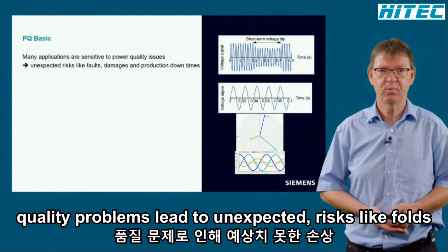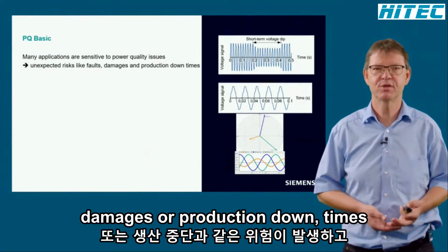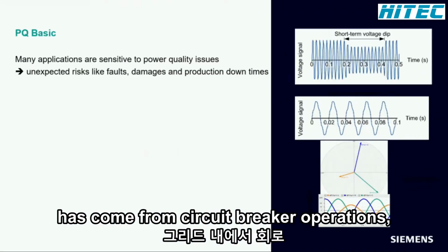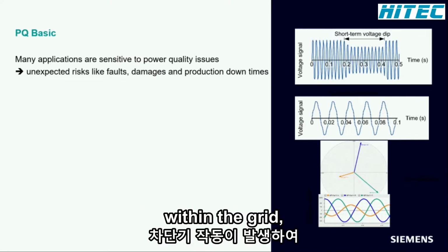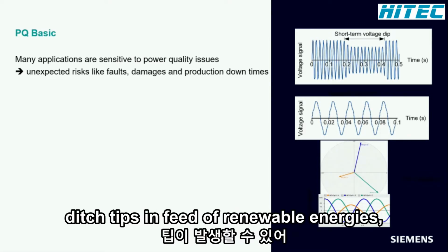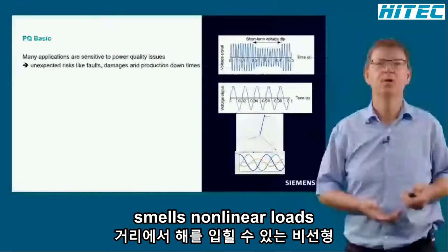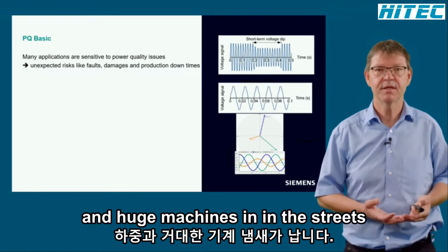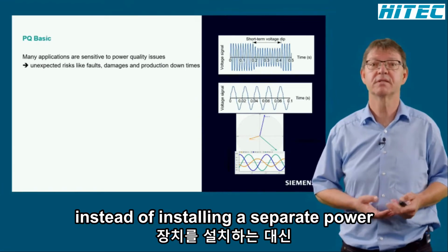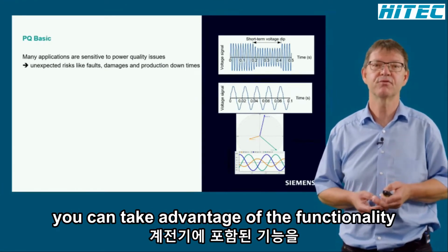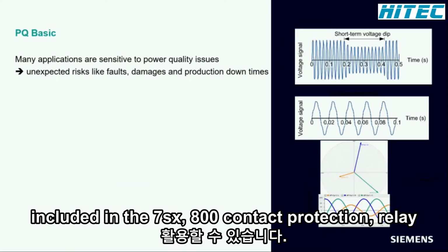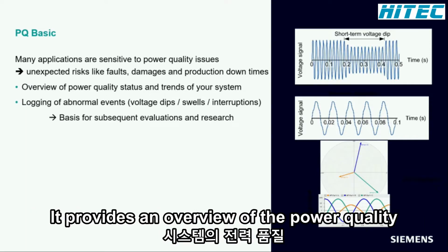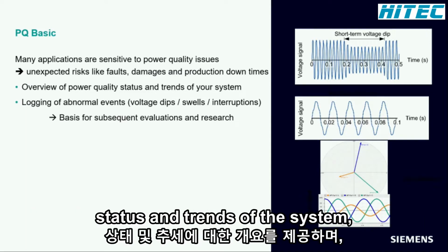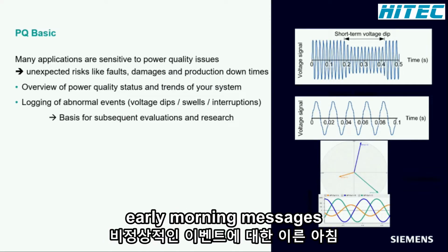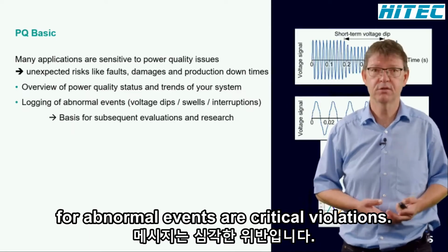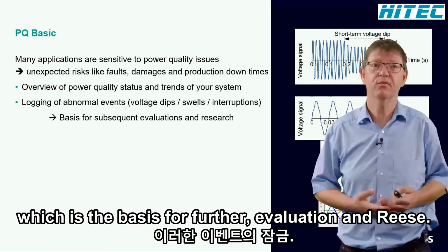More and more power quality problems lead to unexpected risks like faults, damages, or production downtimes. Typically, power quality issues come from circuit breaker operations within the grid, which can cause voltage dips, infeed of renewable energies, which can lead to voltage swells, nonlinear loads, and huge machines in industry that could cause harmonic distortion. Instead of installing a separate power quality device, you can take advantage of the functionality included in the 7SX800 compact protection relay. It provides an overview of the power quality status and trends of the system, early warning messages for abnormal events or grid code violations, and the logging of these events, which is the basis for further evaluation and research.